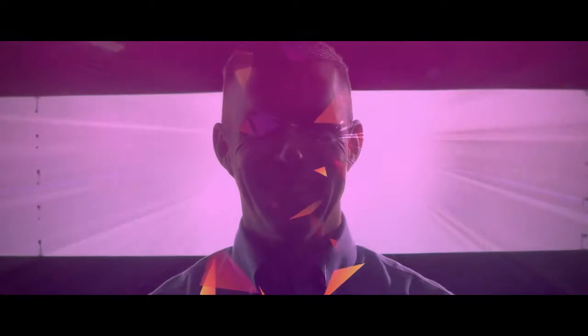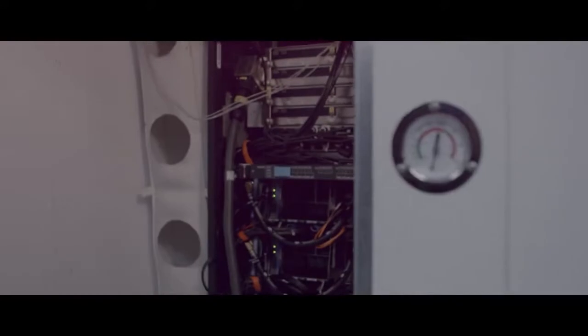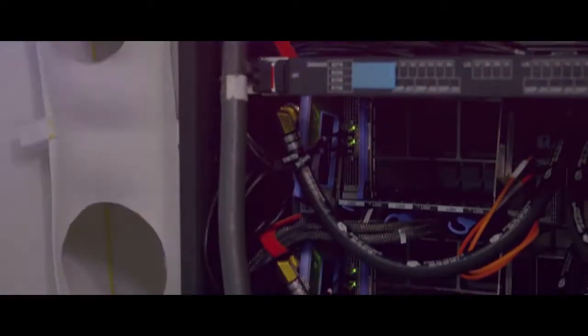So my job as part of the engineering system test team is to try to break the mainframe. But we're doing that towards making it a better and more resilient system for the customer. So in our thermal testing, what we try to do is take the machine up to higher temperature than would ever be seen in a customer data center. And we'll take the voltage and frequency and vary those within the test as well.